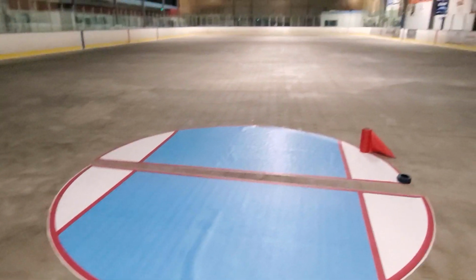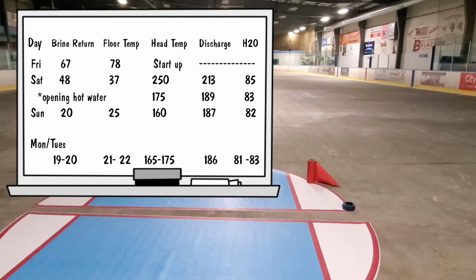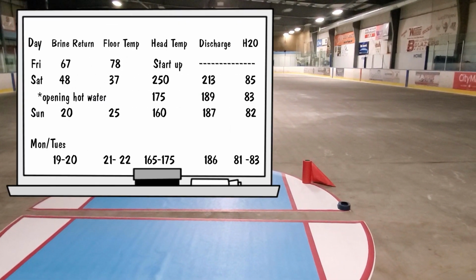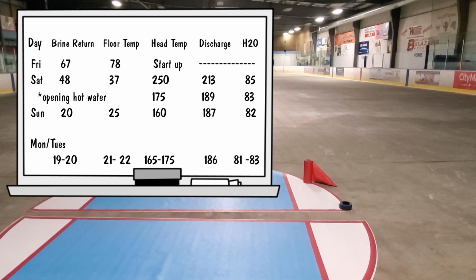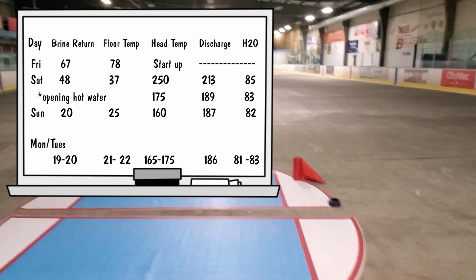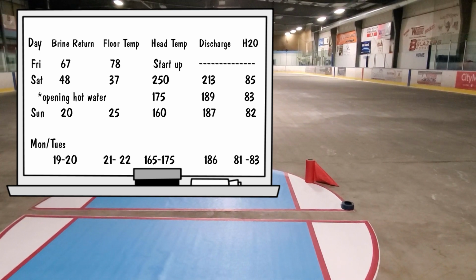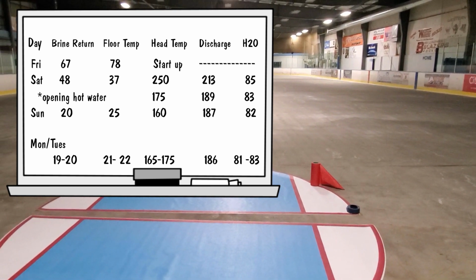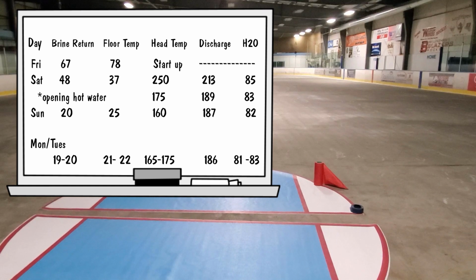From Monday to right now, the concrete was 22 degrees; now we're at 20. Return temperature was about 20 degrees, now down to 19. The pump has slowed down -- not cycled down, but backed off -- we're down to 33%, with only 1 compressor going.